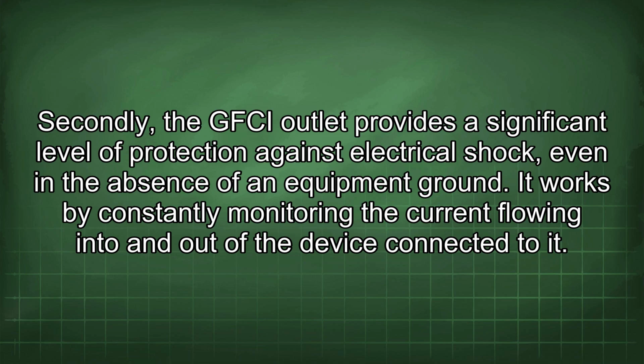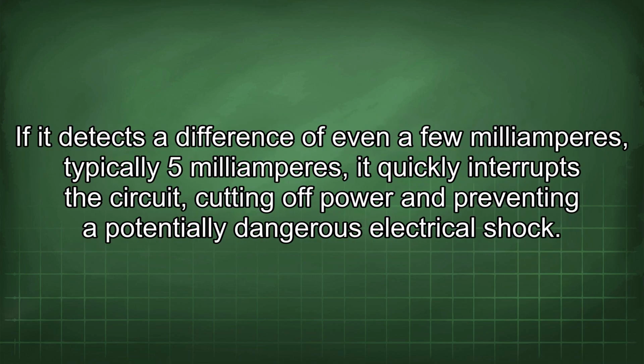ground. It works by constantly monitoring the current flowing into and out of the device connected to it. If it detects a difference of even a few milliamperes, typically 5 milliamperes, it quickly interrupts the circuit, cutting off power and preventing a potentially dangerous electrical shock.